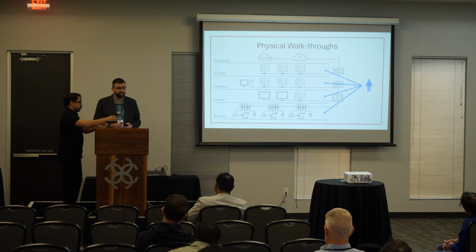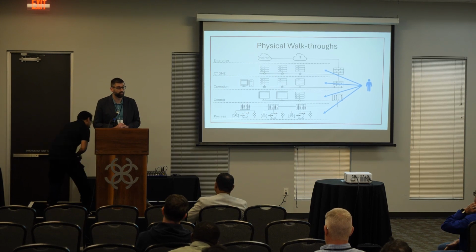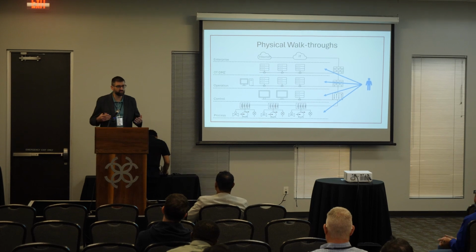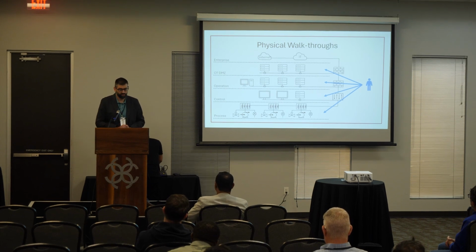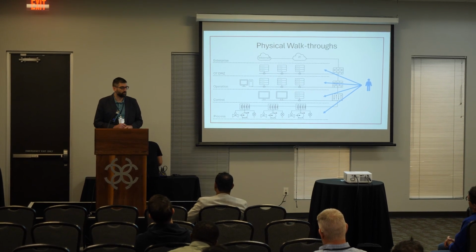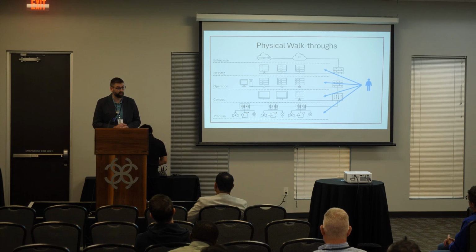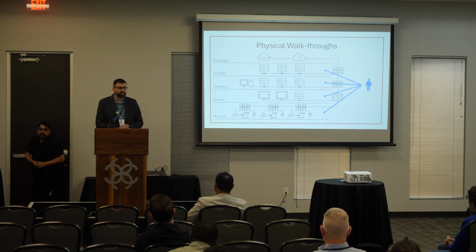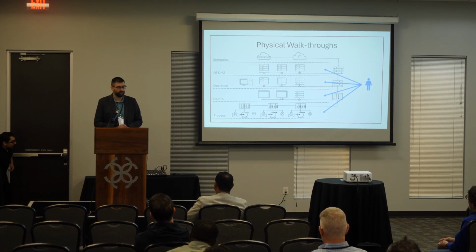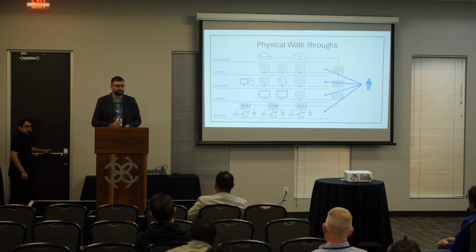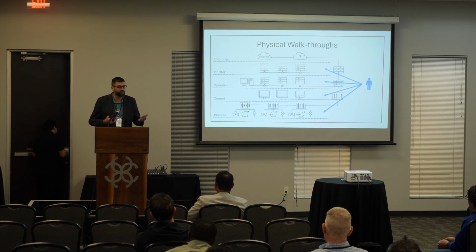consultants and contractors would leave cell modems in PLC cabinets with good intentions of providing support, and I thought that would never happen. It's got to be made up, a little bit exaggerated. So I did a physical walkthrough one day, and okay, here's our PLC cabinet, and I opened it up, and sure enough, there's a cell modem sitting inside, connected to the PLC. Why is that there? Oh, it's so the vendor can log in and troubleshoot for us when they need it. Okay, let's talk about the security risks and see what we can do to mitigate this.